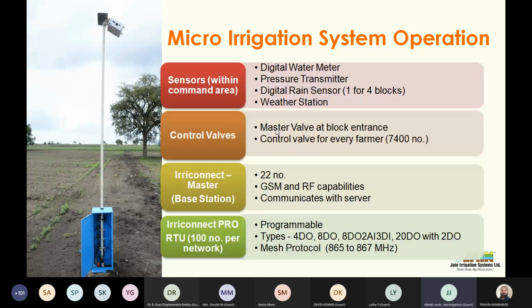There are pressure and flow transmitters. We continuously monitor pressure and flow conditions, because for a water distribution network, the health indicator is pressure and flow. You need to continuously monitor pressure and flow because in a remote area there's always a chance the farmer may open up his valve, or the pipeline may break down, or something may happen, or sometimes a valve is not opened. So you observe the pressure and flow, and if there are alarming situations, alarms will be generated so the field technicians can take care of these requirements.